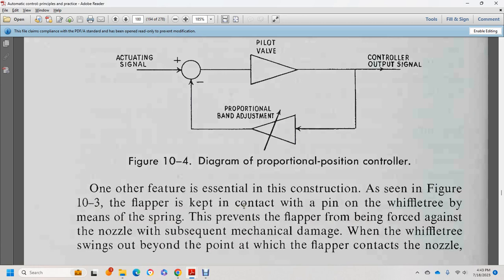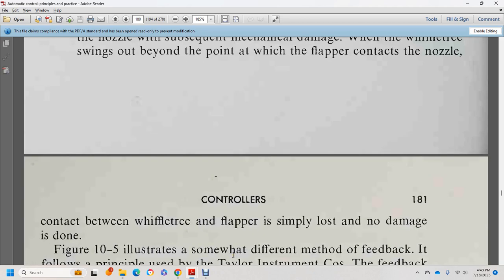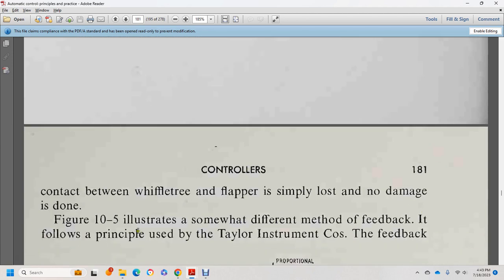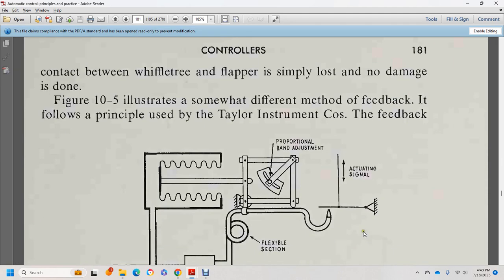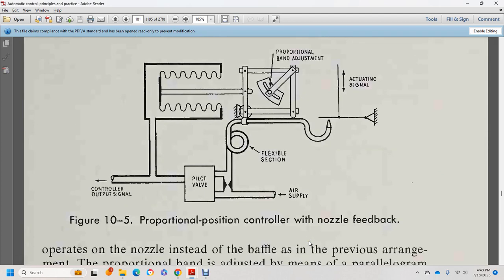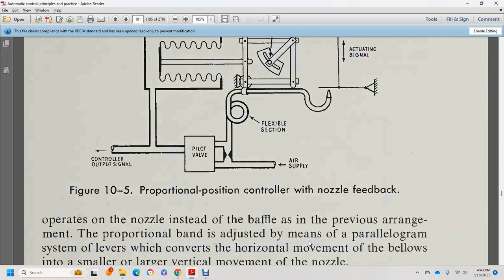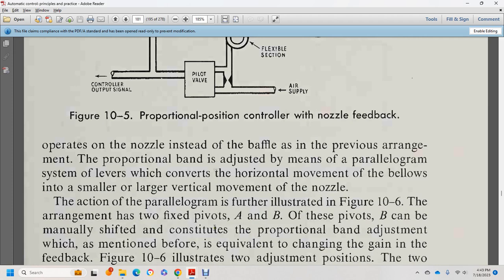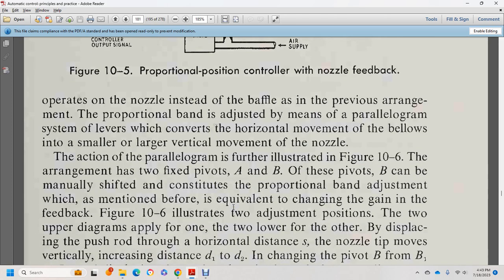In figure 10-3, the flapper is kept in contact with a pin on the whiffletree by means of a spring. This prevents the flapper from being forced against the nozzle; if the whiffle tree swings beyond the point of flapper contact with the nozzle, contact is simply lost with no damage done. Figure 10-5 illustrates a different method of feedback, following the principle of the Taylor Instrument Company. The feedback operates the nozzle instead of the baffle. The proportional band is adjusted by means of a parallelogram lever system.